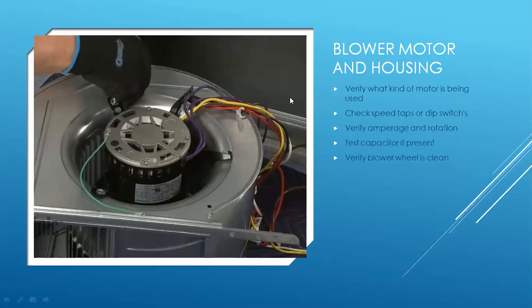So you have your blower motor in your housing. That's how it's supposed to look right here. Nice and shiny and clean. That looks pristine. It is important to understand what kind of motor you're using. Is it a PSC motor with a capacitor? Is it an X13, which is a pre-programmed ECM? Or is it an ECM variable speed? Verify and check your speed taps and/or your dip switches and/or your thermostat, depending on what you're doing.